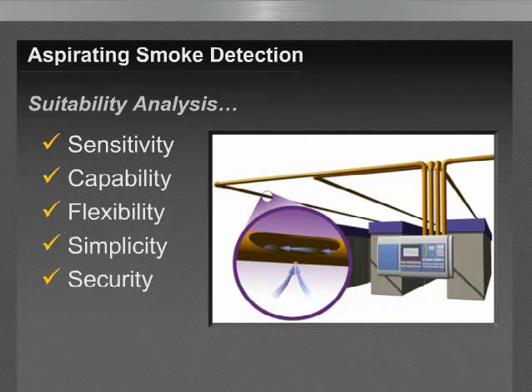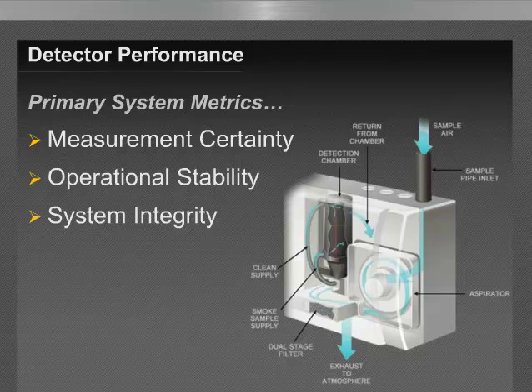In addition, ASD air sampling detection offers exceptional performance, as demonstrated in the primary system metrics, which include certainty of measurement, and that is absolute high stability, fixed calibration, alarm thresholds between 0.0015 and 6.4% obscuration per foot, and an optical light scattering detection principle using a solid-state laser light source. And we talk about operational stability and the higher tolerance and rejection of nuisance alarms caused by dust, steam, insects, and so forth, and high stability optics. And system integrity, the fact that active monitoring of all critical detector functions occurs, such as flow, optics, and calibration, and the fact that in some systems optics are automatically cleaned, requiring no drift compensation techniques or calibration of the detectors once installed.